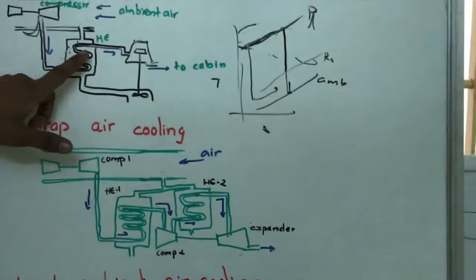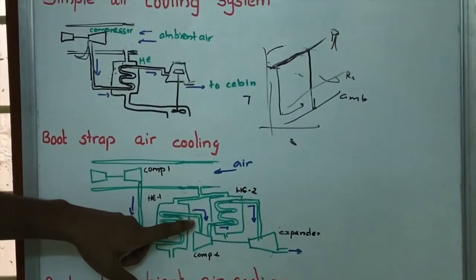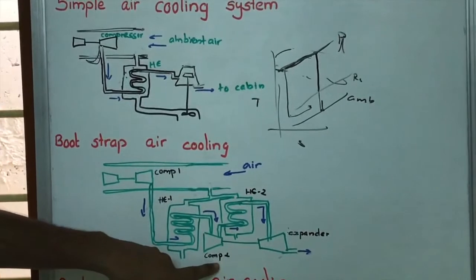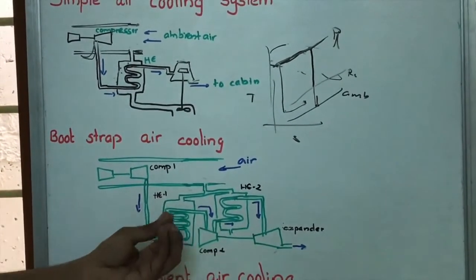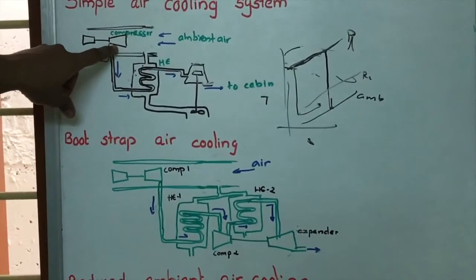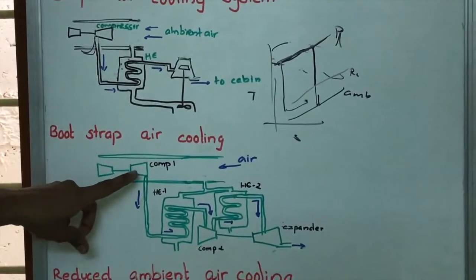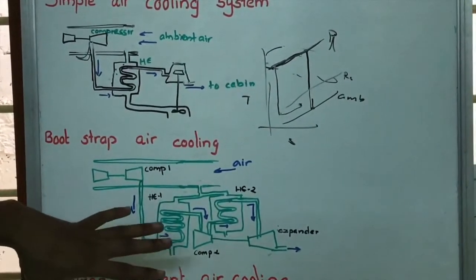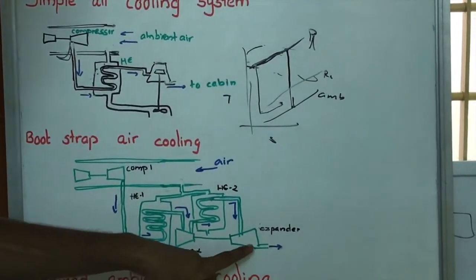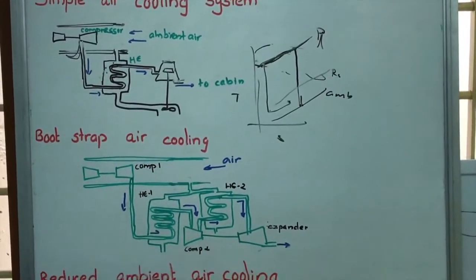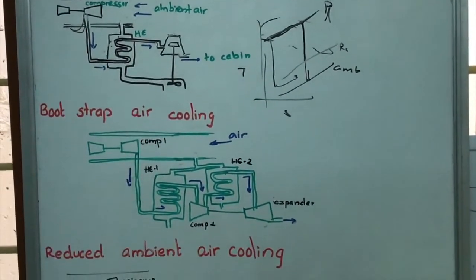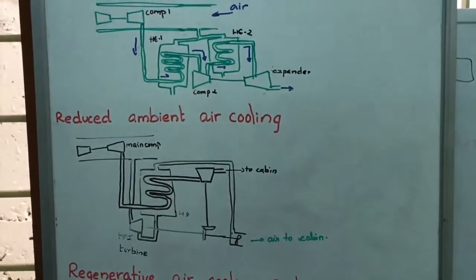In the bootstrap air cooling system, the same process occurs, but after the first heat exchanger a second compressor is added so that the air is compressed once again. It is then fed to another heat exchanger to reduce the temperature again, and finally fed to the expander. In the simple system, compression is achieved only once, but in the bootstrap system two compressors allow much greater compression. With more compression, the expansion in the expander is greater, resulting in a larger temperature reduction and increased cooling effect.